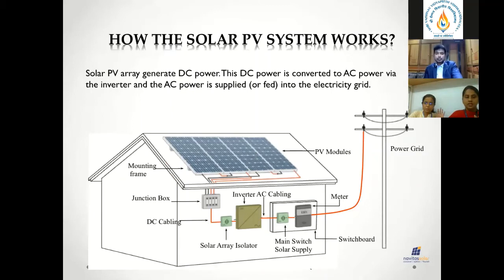You will see a frame module mounted over the roof, connected to the junction box, which combines the DC voltage and current. Then with the DC cable - in solar we generally use a special type of cable called XLPO, cross-linked polyolefin cable - which is a totally UV protected cable, and we follow different standards for using it.